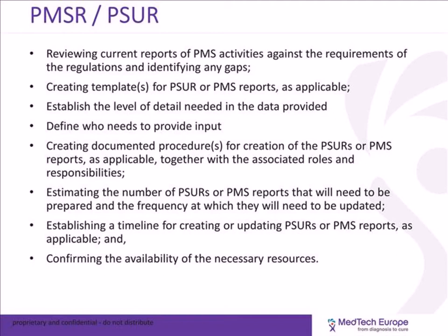Estimation of the workload and number of reports here as well has to do with the product portfolio composition. Depending on whether you carry low risk or high risk, the workload will be very different and should be built, and I may sound like a broken record here, but should be built as a maintenance cost, because if these reports are not produced, the product will not be able to be maintained on the market after the date of application.